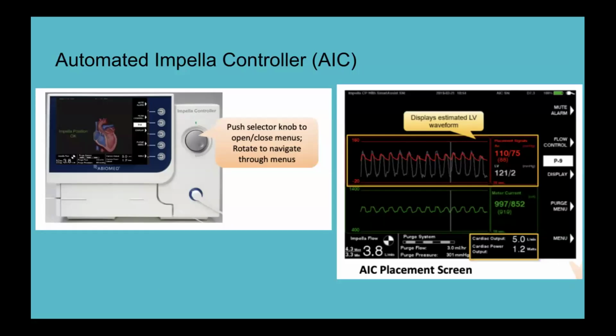So with every Impella CP comes an automated Impella controller. I kind of think of this as our interface for both monitoring and controlling the device. When you look at this device, some of the pro tips are, if you look at the top left of the screen, it's going to tell you the exact device you have, in case you're not sure which Impella you've got. It also tells you the P level, over on the right side, and this is also how you would adjust that P level up and down. This is also where the purge fluid, which I'll discuss in a moment, is controlled and maintained from.